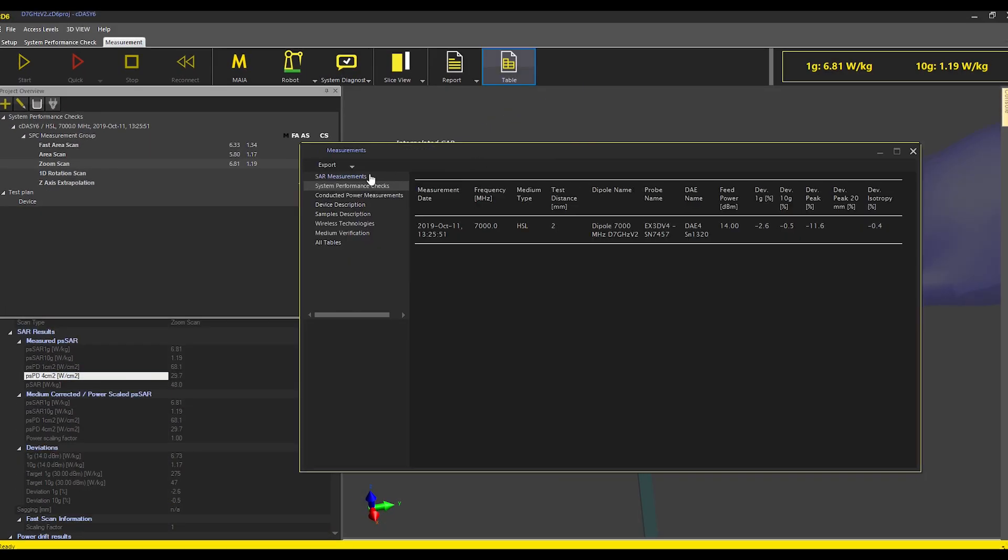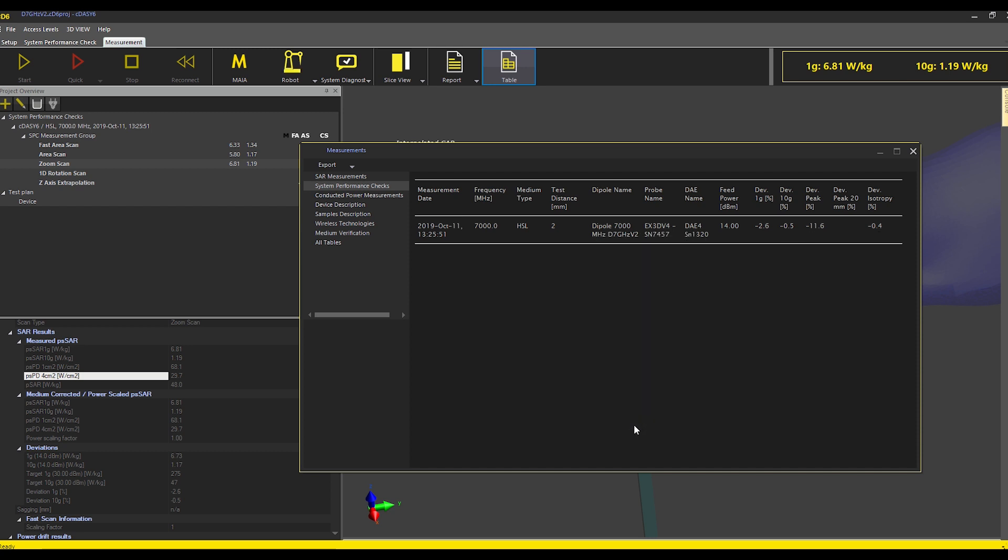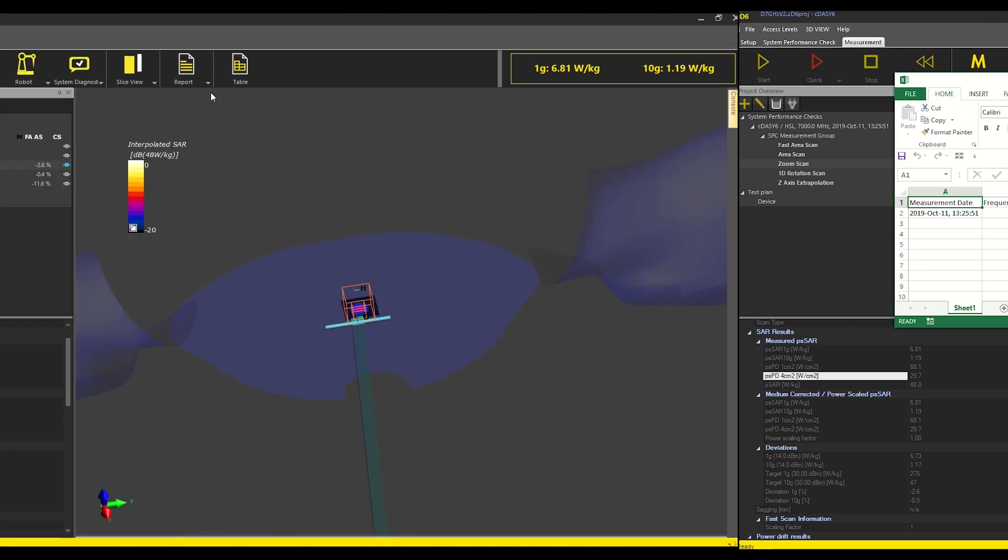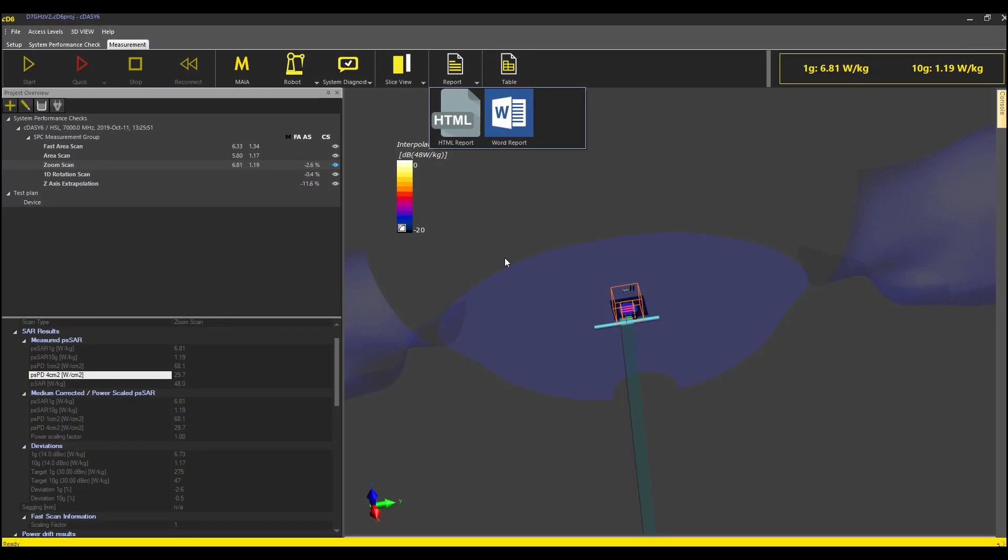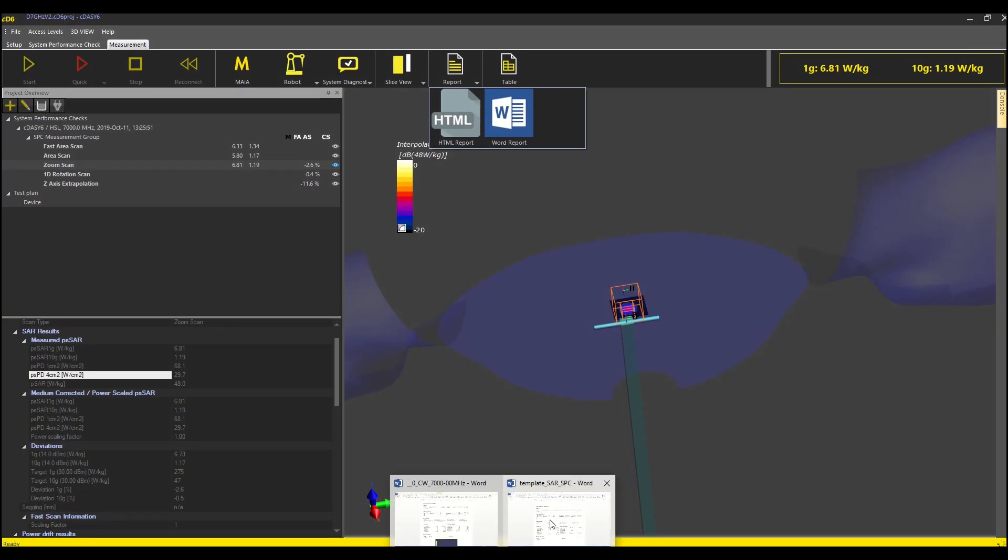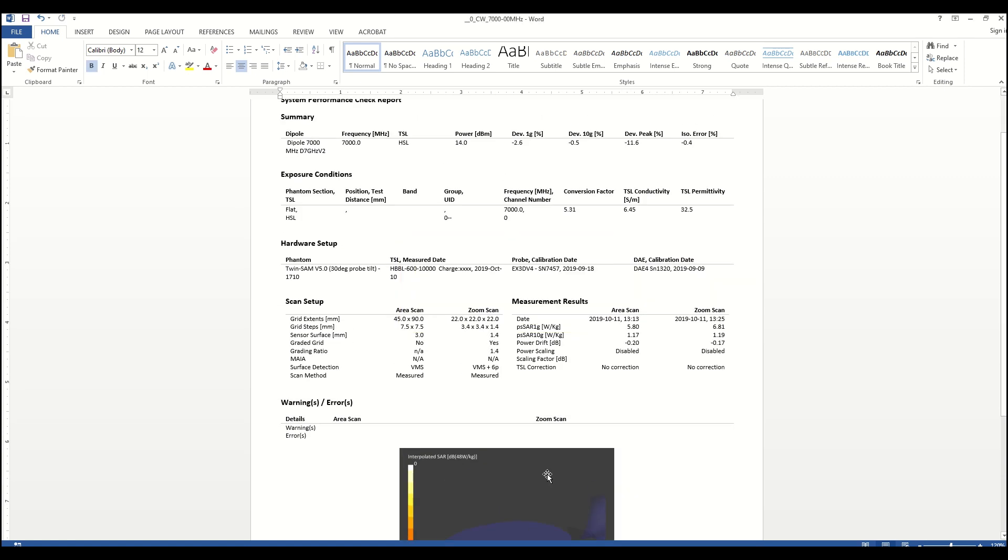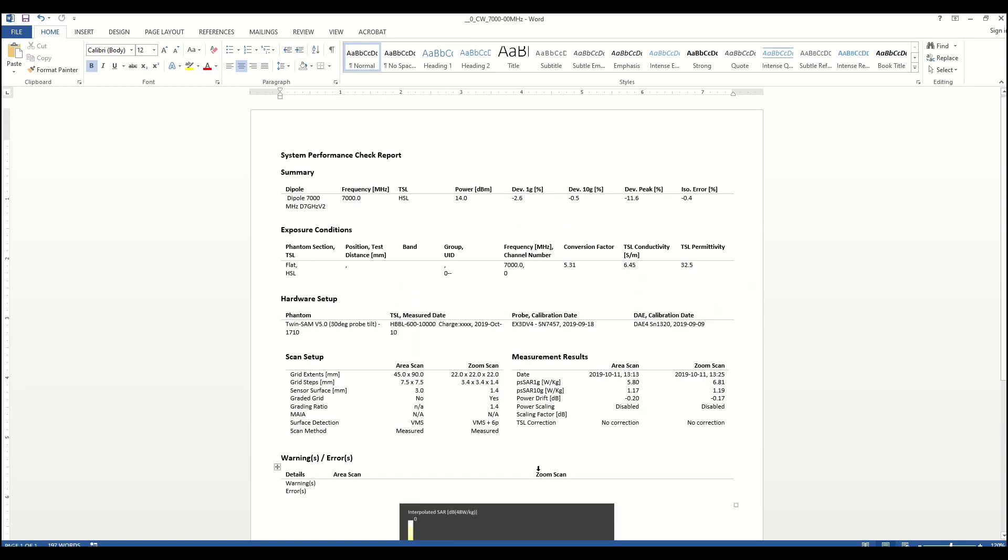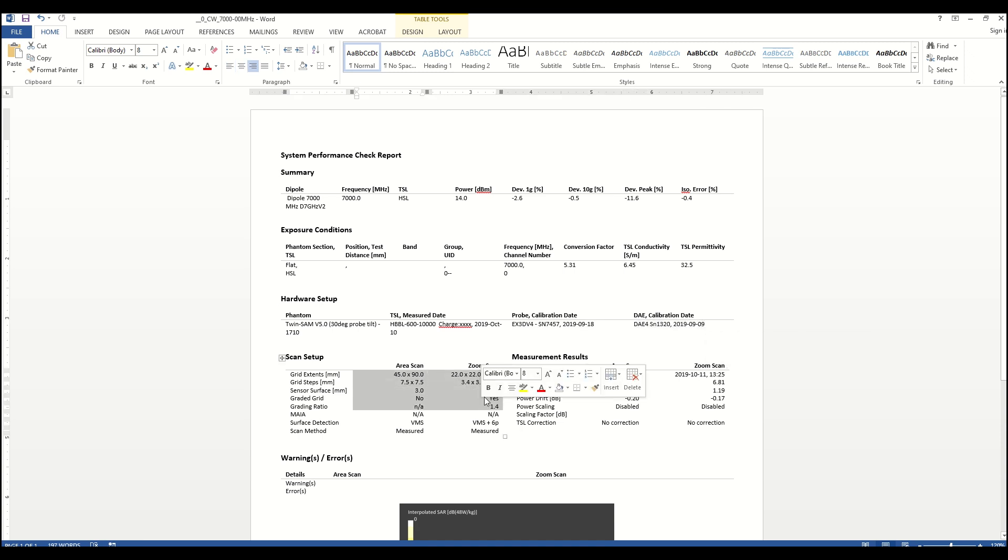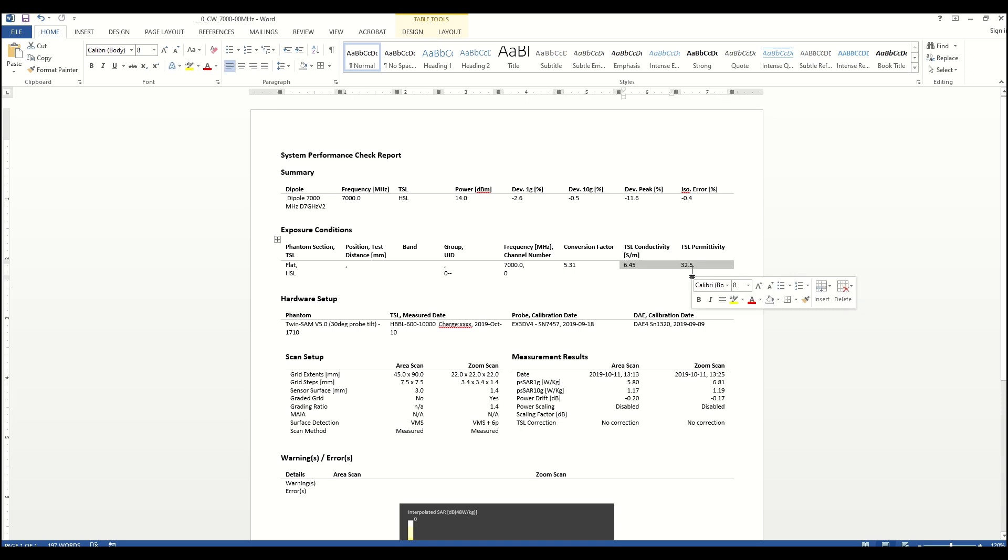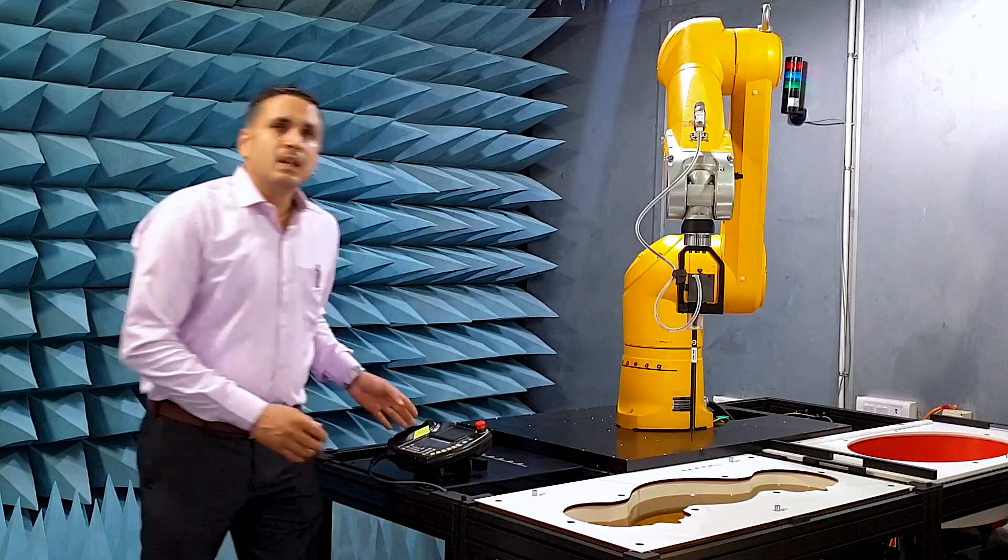The system check results are available in tabular form for export into Excel. It is also possible to generate reports with plots for individual measurements using the word report option here. The word report includes all details such as the probe or DAE, scan settings, HSL values and also the measured SAR or power density values and their deviations from targets.